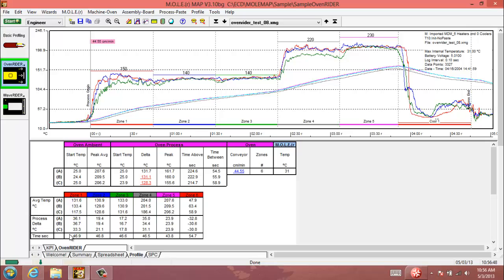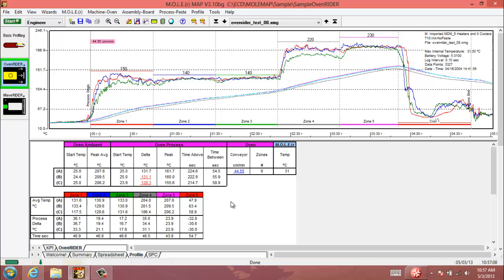It'll also display how much time the sensor spent in each zone for your oven run. So it's a very handy tool for keeping track of your oven, verifying that it's not leaking heat anywhere, or troubleshooting any type of convection issues with the oven.